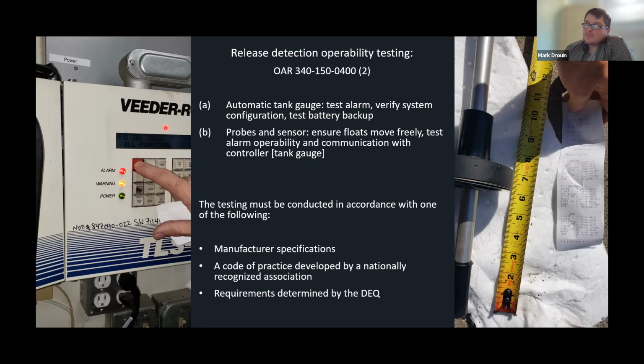In general, we want to make sure that this tank gauge, this specific Veeder-Root as an example, there could be others, Incon, and a few others out there, goes into alarm. If there's ever an issue with your probe, this is a tank probe that goes into your tank, and there's a catastrophic release and all of a sudden you lose 10,000 gallons of fuel, as a bad example, we want to make sure that this Veeder-Root goes into alarm. So that's what we want tested: does this alarm?